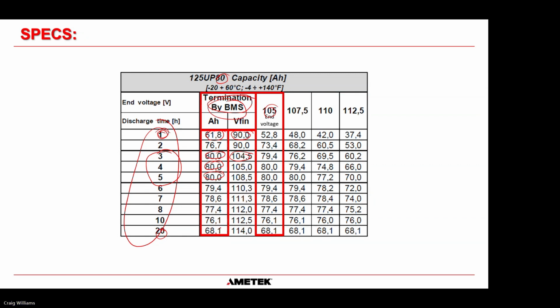Okay. What I don't quite understand is they're saying that at the 20 hour rate, you'll get 68.1 ampere hours, but the BMS will terminate at 114 volts. I don't quite understand what it's saying there. It confuses me because it's saying here that at 105 volts, you will still get 68 ampere hours as well. So not quite sure. This is a newer technology, so their discharge table doesn't make a huge amount of sense to me at this moment in time.